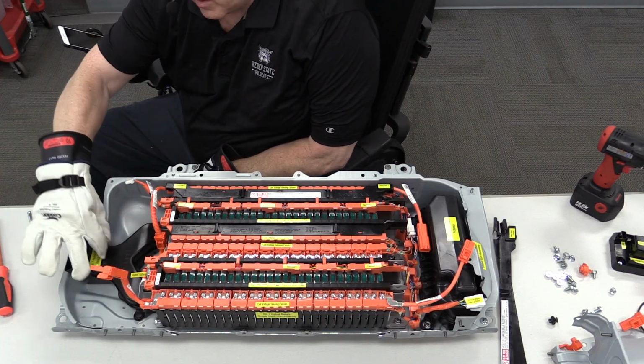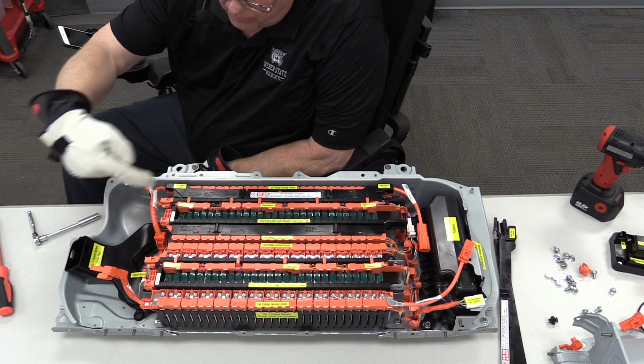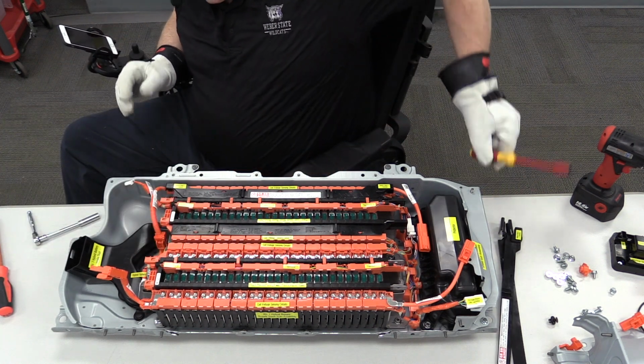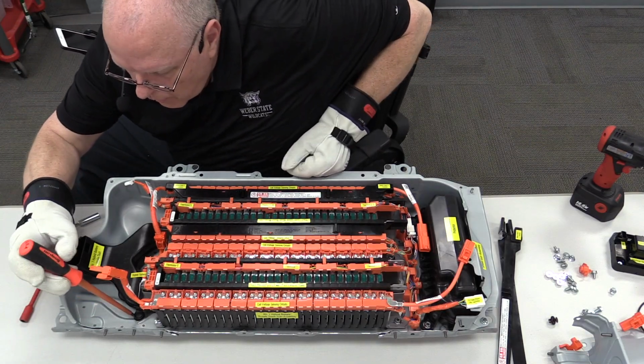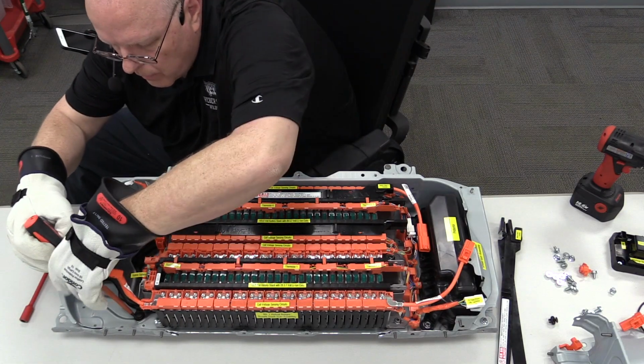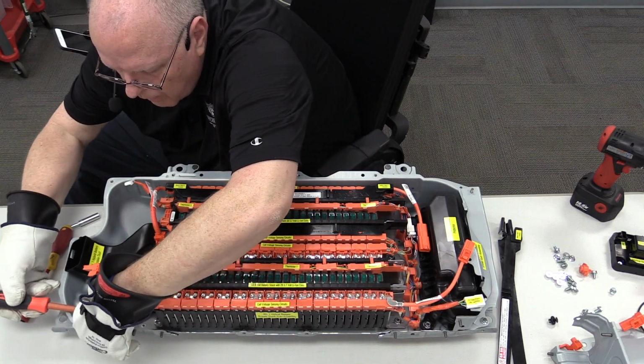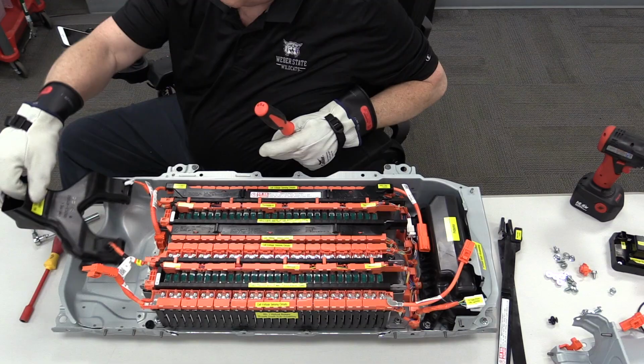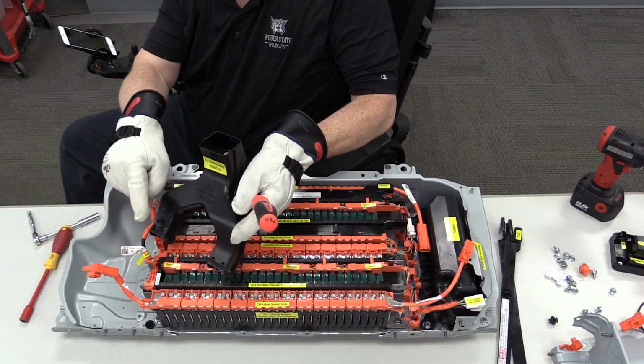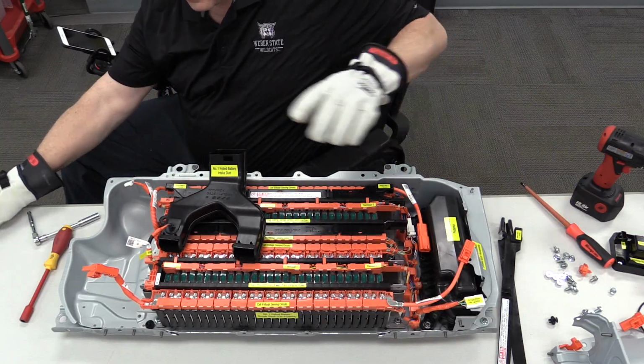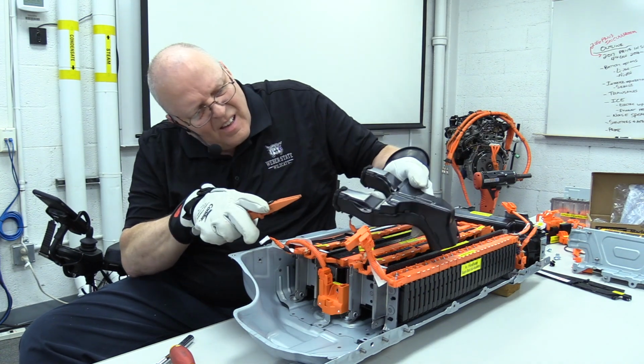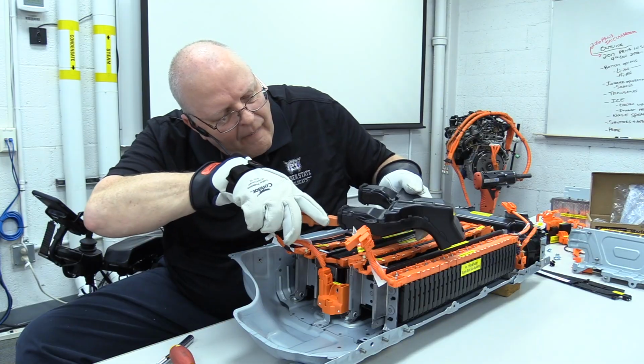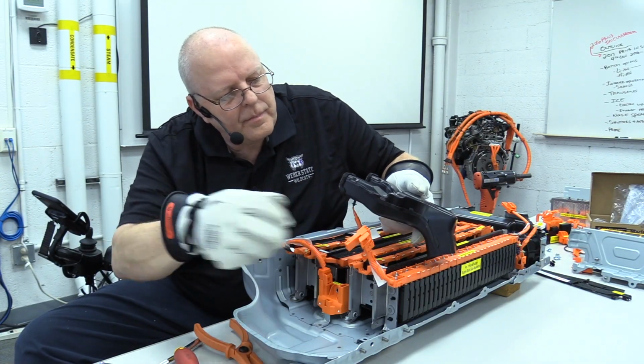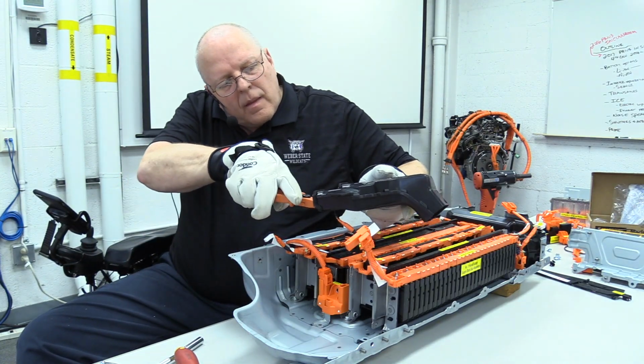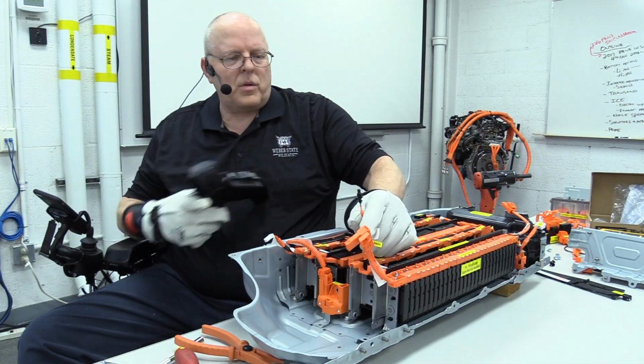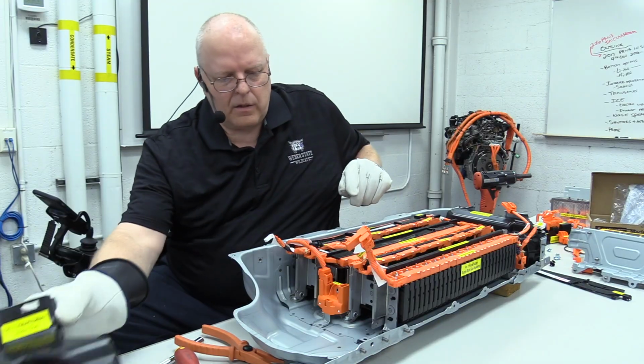Now we can see the intake duct where it splits into 2 inlets, one for underneath each battery stack. This has a little plastic clip that holds it in place also. Right there, and then that just pulls out. It has a temperature sensor, an inlet temperature sensor, that has 2 little squeeze tab locks on the inside of it. Two little squeeze tabs right there. And we'll set our inlet out of the way.